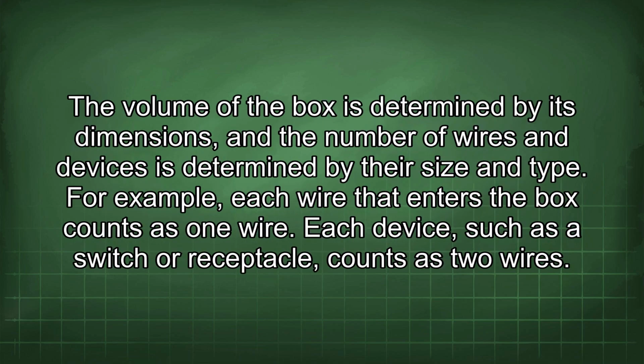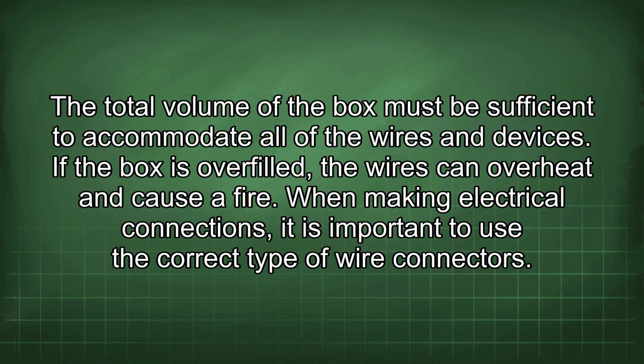The volume of the box is determined by its dimensions, and the number of wires and devices is determined by their size and type. For example, each wire that enters the box counts as one wire. Each device, such as a switch or receptacle, counts as two wires. The total volume of the box must be sufficient to accommodate all of the wires and devices. If the box is overfilled, the wires can overheat and cause a fire.